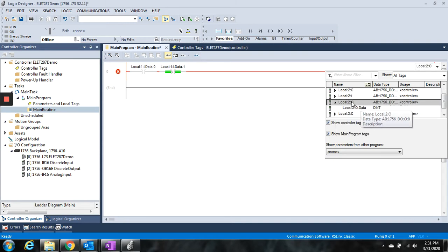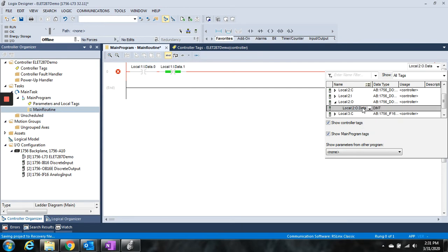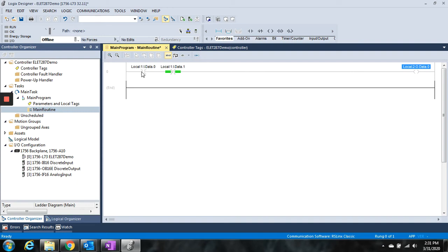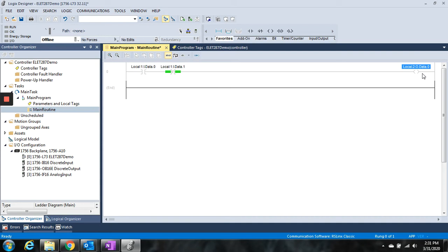So we're going to go local 2:O, and then data, and we'll tie it to the first output. And there we go. We've got a simple ladder logic where my first input on my input card, if that turns on, and then if my second input on the input card, if it is not on, since it's normally closed, then I will turn on my output to the output card.